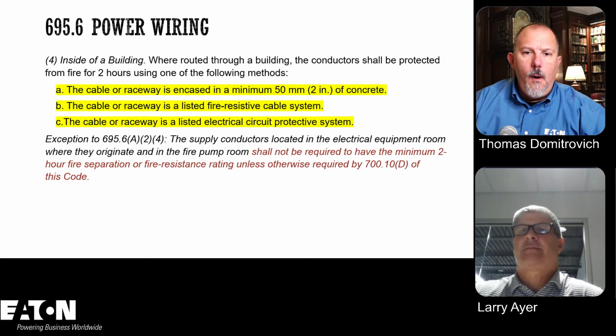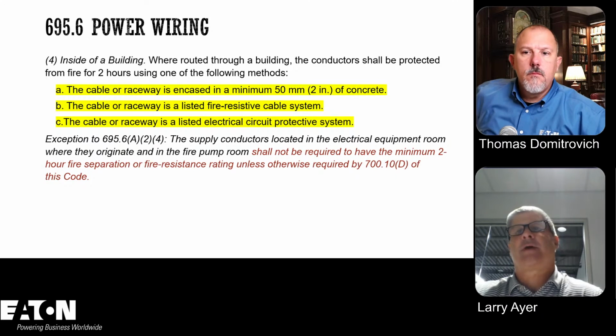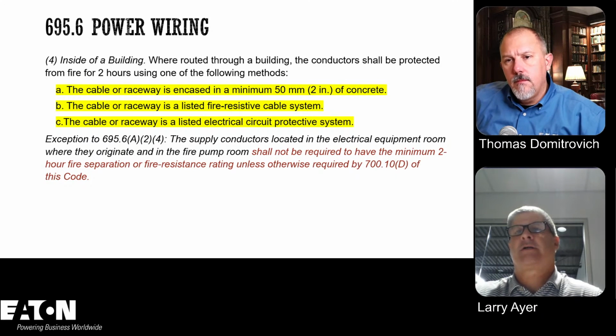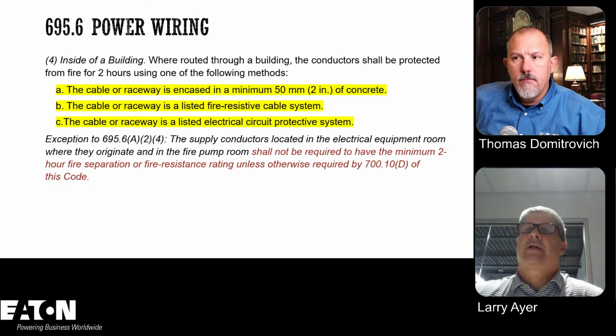If you're going to route inside a building, you're going to have a cable or raceway encased in 2 inches of concrete, or you're going to have to put it in a raceway that's a listed fire resistance cable system, or you're going to have to have a listed electrical circuit protective system.